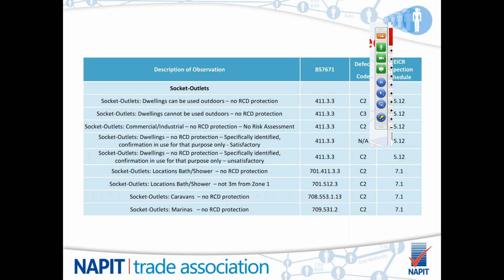On sockets, a lot of questions are asked about whether a socket needs RCDs on it. BS 7671 states that any socket up to 32 amps requires RCD protection, but of course previous installations were not wired or installed to those standards. If a socket outlet could be used outdoors and it doesn't have any RCD protection, that would be a C2.